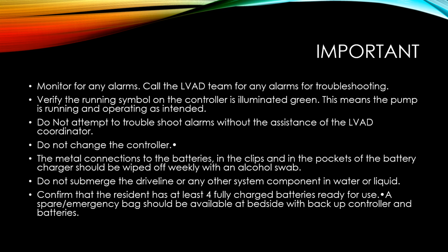It's important that the nursing team monitors for any alarms. Call the LVAD team for any alarms for troubleshooting. Verify that the running symbol on the controller is illuminated green. This means the pump is running and operating as intended. Do not attempt to troubleshoot alarms without the assistance of the LVAD coordinator. Do not change the controller.